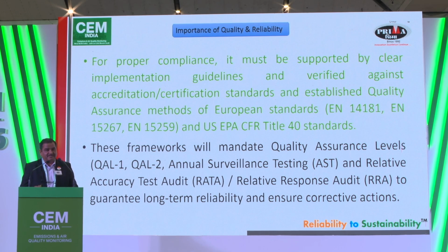The most important one, which probably has not come into the discussion since morning, but is the first step, is 15259, before you install any certified product in your stack. And obviously the CFR method of US EPA. These frameworks mandate quality assurance levels QAL 1, QAL 2, annual surveillance testing, and relative accuracy test audit as per US EPA and the RATA, which gives you long-term reliability after the installation of the certified product.